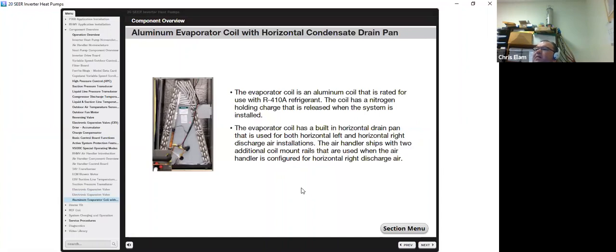The aluminum evaporator coil with the horizontal condensate drain pan. The coils are all aluminum, as you can see, except for the aluminum copper connection. It's rated for 410A refrigerant. The coil does have a holding charge of nitrogen that needs to be released when the system is installed. The evaporator coil has a built-in horizontal drain pan that is used for both horizontal left and horizontal right discharge air installations. The air handler ships with 2 additional coil mounts, coil rails, that are used when the air handler is configured for a horizontal right air discharge.